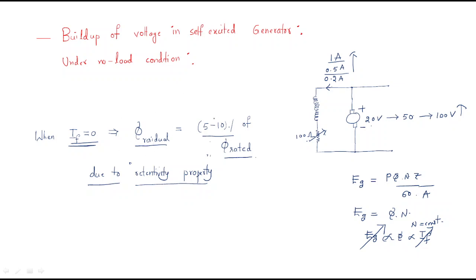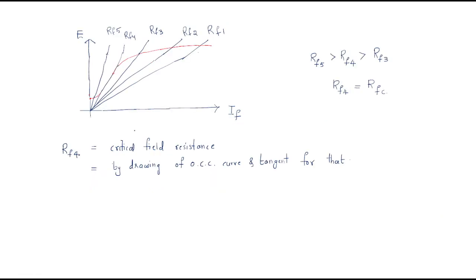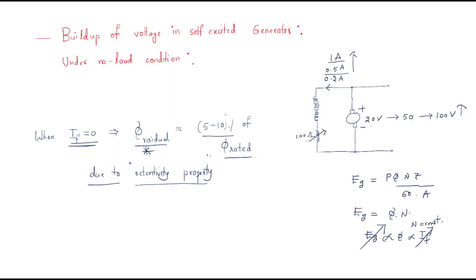This is the main reason for the self-excited generator's voltage buildup. If there is no residual flux, there is no generated EMF in the self-excited generator. That's why residual flux has higher priority and is very important.